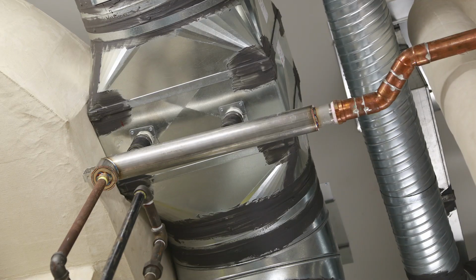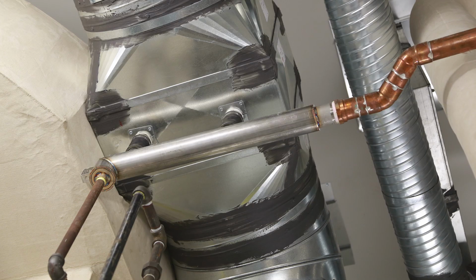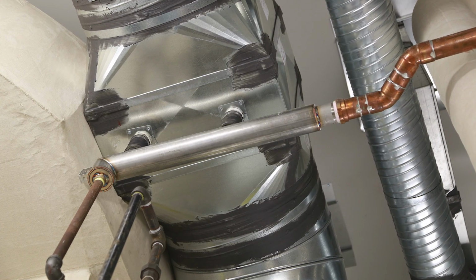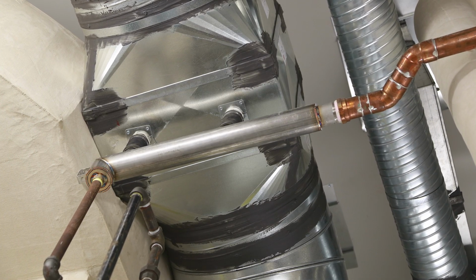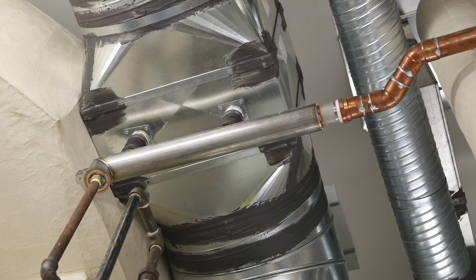In that case, you're typically looking at a branch duct. Or maybe you've got a hospital and you're trying to humidify the entire building to a reasonable level, but you have a burn unit that needs to be at a higher level. Well, you could do the base level at the air handler and then add an additional one, basically a trim, in order to handle that special space. So you can get it beyond its base level to where you want it for that specific space. That way you don't have to size it as large.